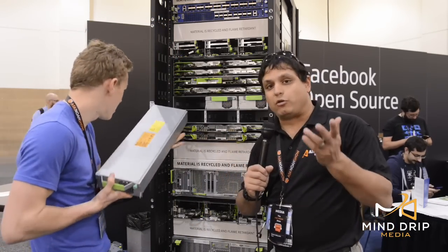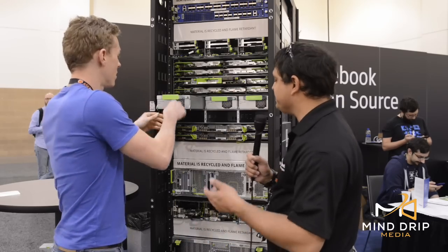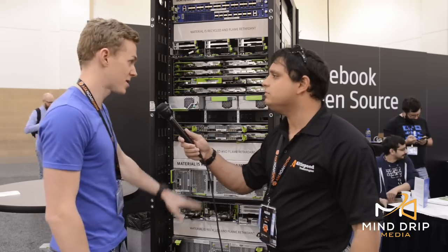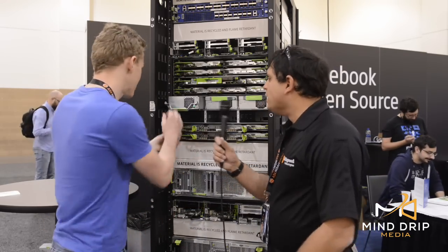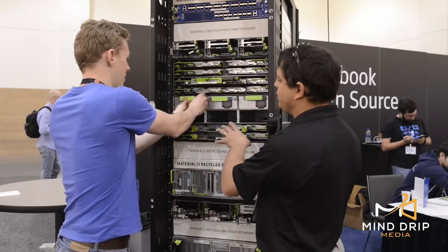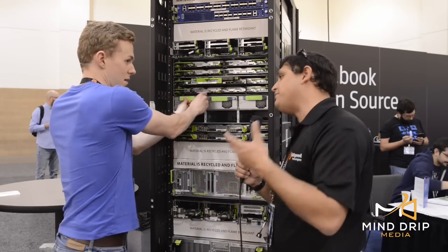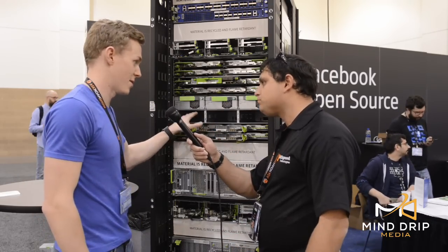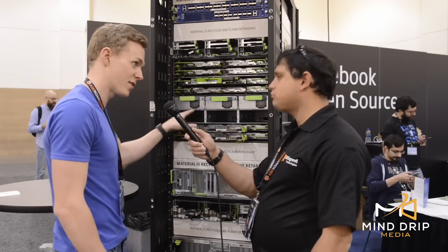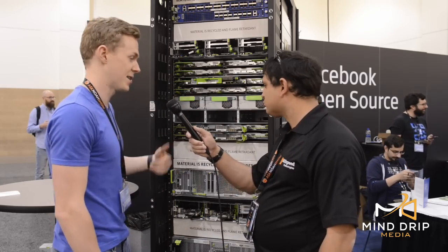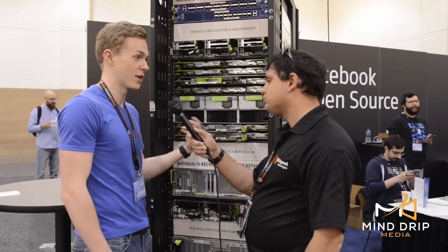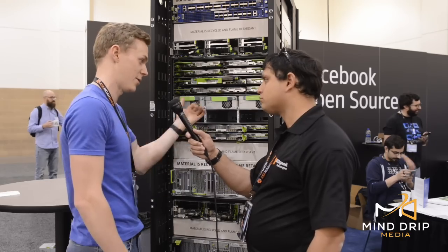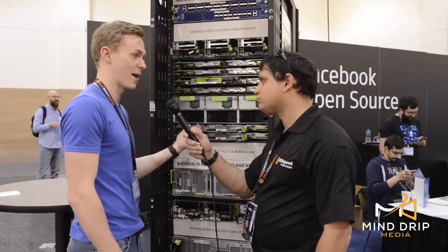The average power draw, power budget, as they put it, is 10 to, I think you said 10 to 12 kilowatts? That's right. You have 3 of these up here and 3 below, so between all 6, you're doing 10 to 12 kilowatts. Now, the batteries are required, like you said, to run the unit. Now, that's not actually a physical requirement. They've actually enforced that in firmware. That's right. So if you were able to look at the back of this unit, there's a management controller, and it is able to tell you the status of these power supply units and the status of the batteries, and it's able to run tests on the batteries to make sure they're performing optimally, can drain them down, bring them back up, make sure they don't explode, those sorts of things. So it can be doing testing all the time and ensuring this thing is running optimally.